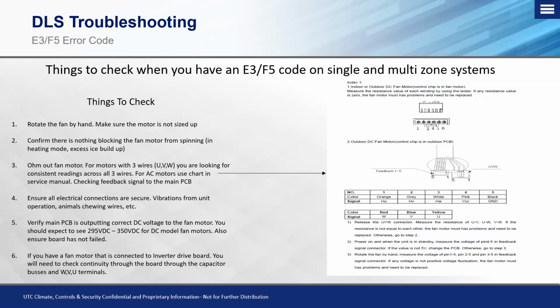Now, in this case, if you're looking at a situation or an outdoor unit that has an inverter drive board, and you verify either through myself on the phone if we're troubleshooting, or if you're going through the wiring diagram on there, you want to verify where your fan motor is connected to. If it is connected to the inverter drive board, the same rules apply. So you're still going to have a U, V, and W that you need to ohm out. You want to verify that you have correct DC voltage coming out from that unit. Again, it depends on what your input is.